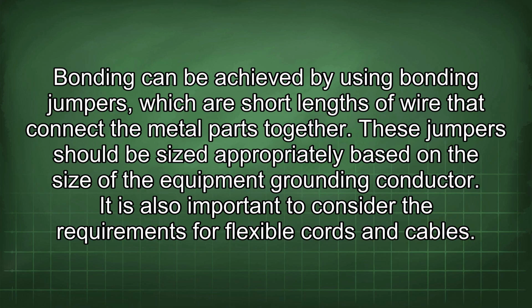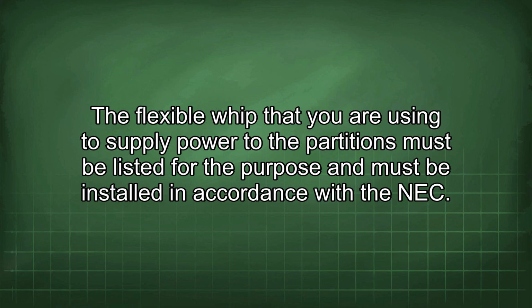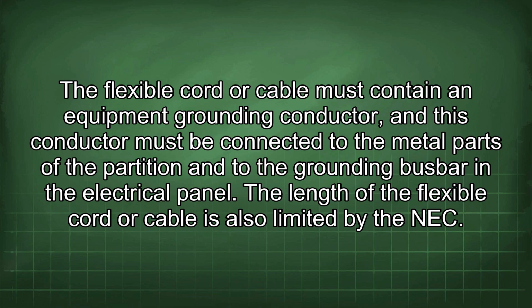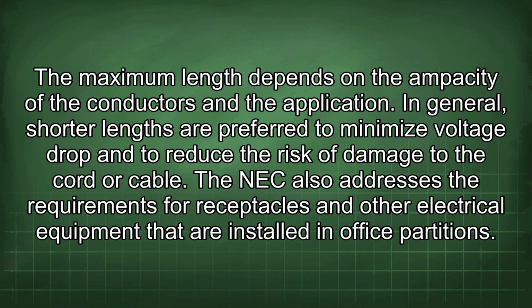It is also important to consider the requirements for flexible cords and cables. The flexible whip that you are using to supply power to the partitions must be listed for the purpose and must be installed in accordance with the NEC. The flexible cord or cable must contain an equipment grounding conductor, and this conductor must be connected to the metal parts of the partition and to the grounding busbar in the electrical panel. The length of the flexible cord or cable is also limited by the NEC. The maximum length depends on the ampacity of the conductors and the application. In general, shorter lengths are preferred to minimize voltage drop and to reduce the risk of damage to the cord or cable.